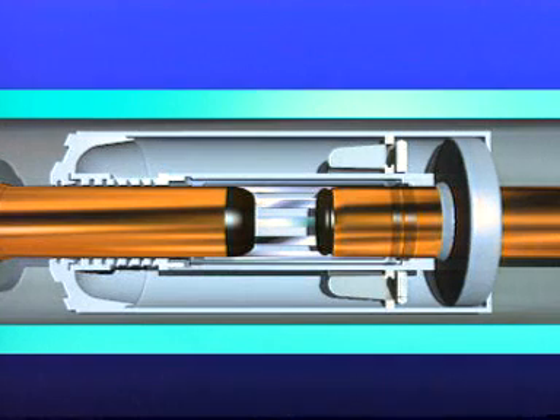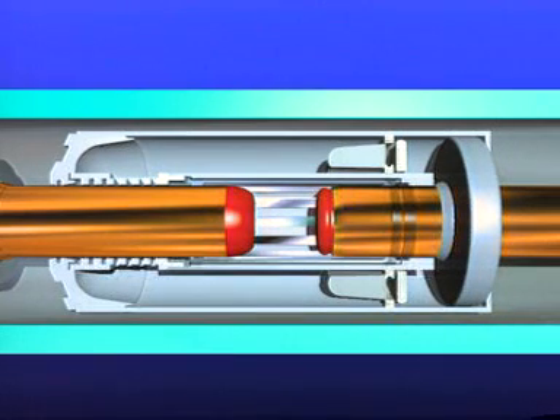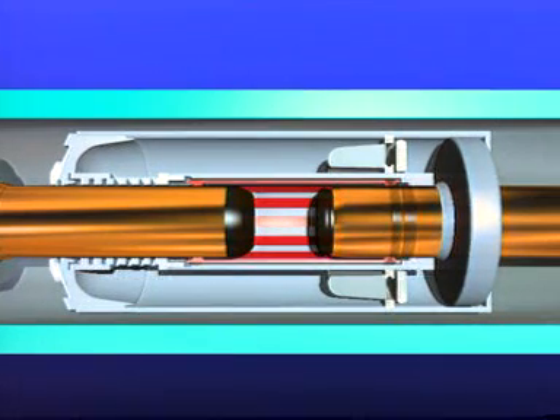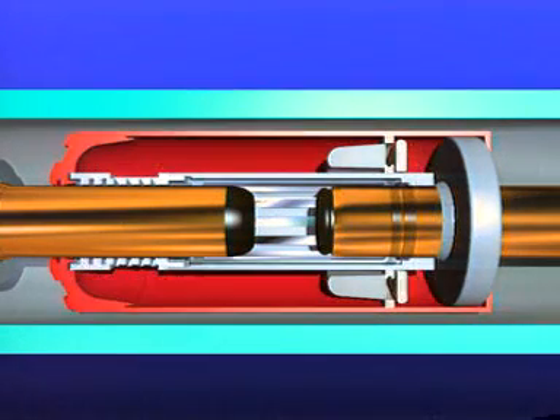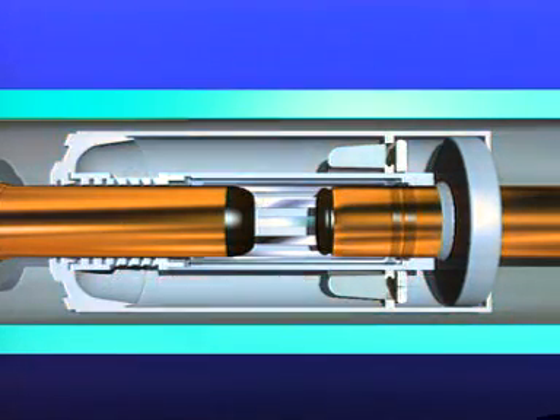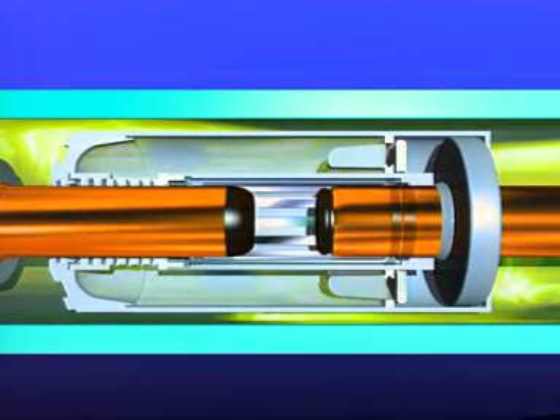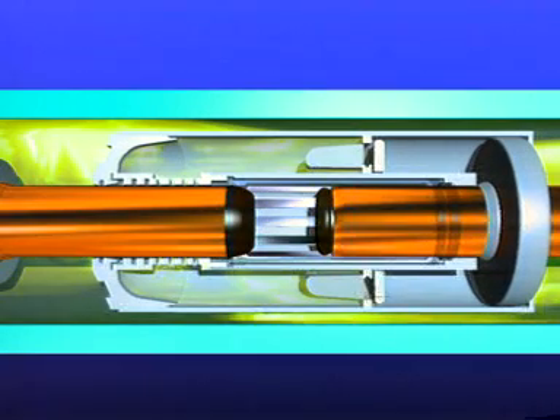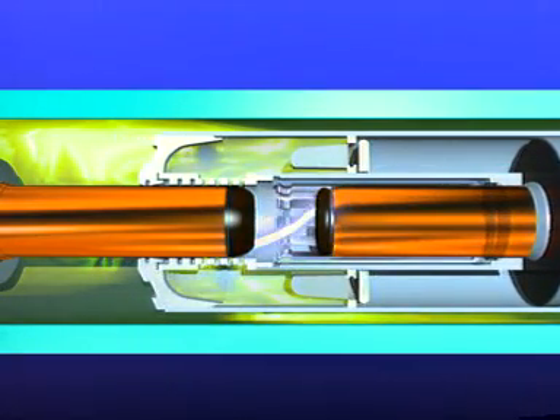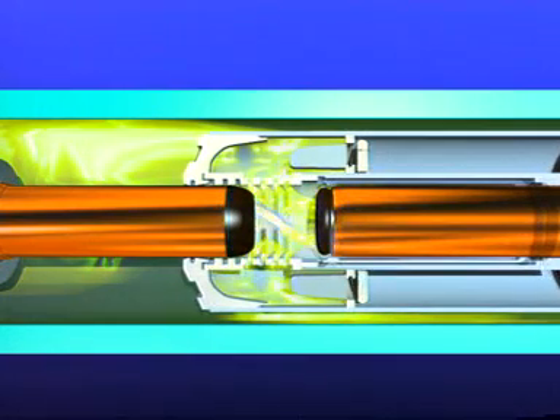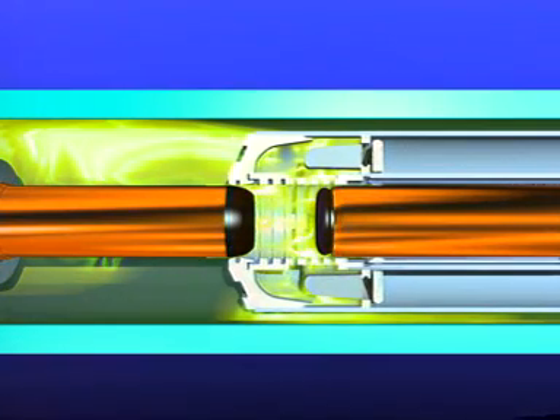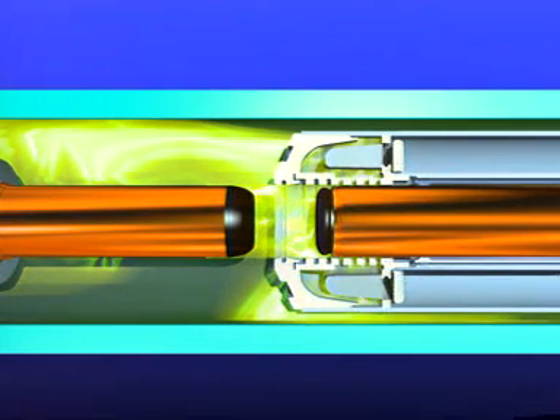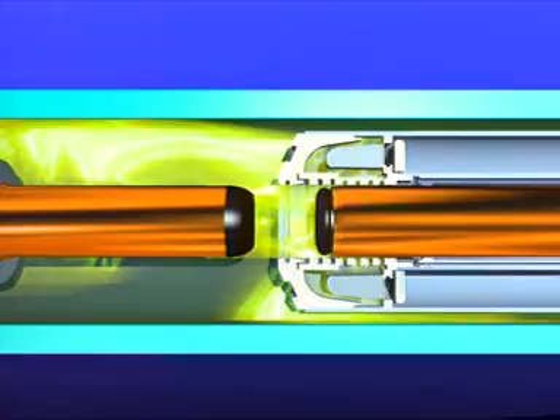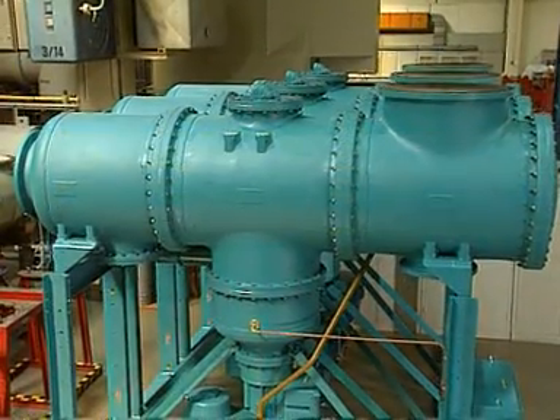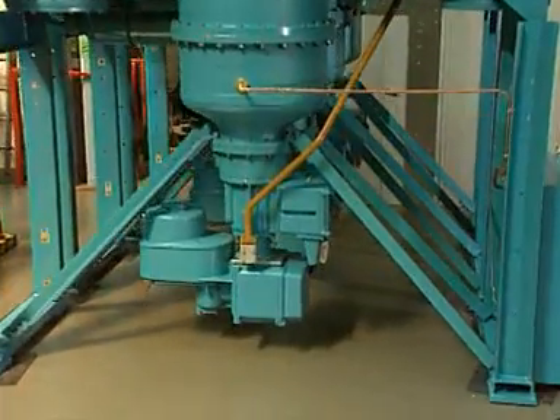Its interrupter units operate in accordance with the well-proven puffer principle. Two quenching nozzles made of arc-resistant graphite are bridged by the moving contact tube with spring-mounted contact fingers. The puffer cylinder grips over it. The complete circuit breaker is filled with SF6 gas. On contact separation, the cylinder and the puffer piston compress the gas contents. The blast lattice releases the flow of gas. This cools the arc and blows it into the quenching jets. In only a few milliseconds, the arcing gap reaches its dielectric strength without restriking. This switching operation calls for considerable operating energy. This is provided efficiently and reliably by an electro-hydraulic mechanism.